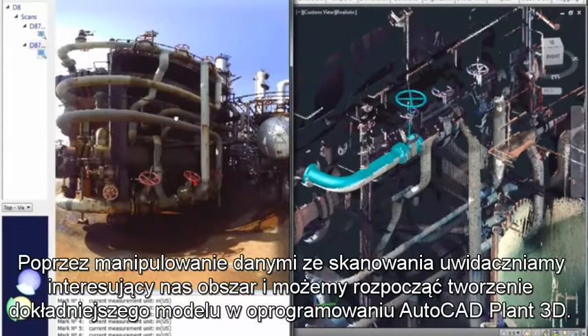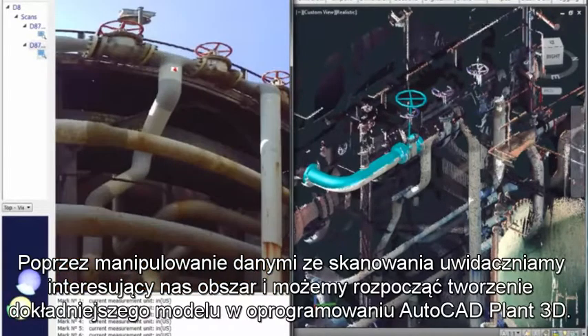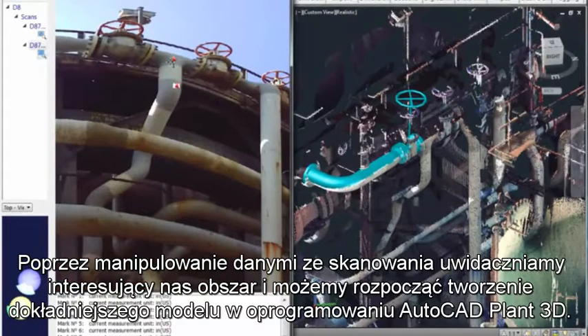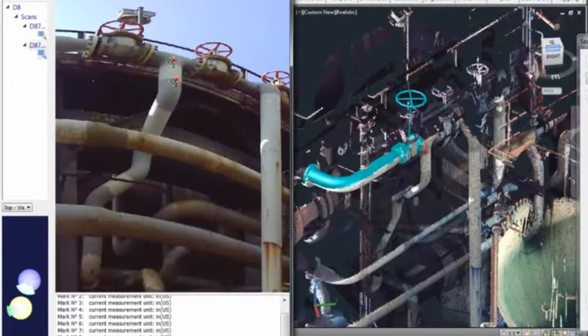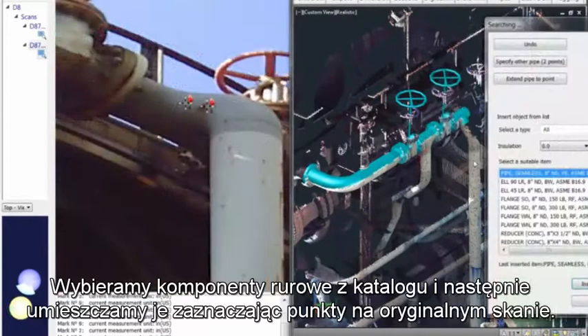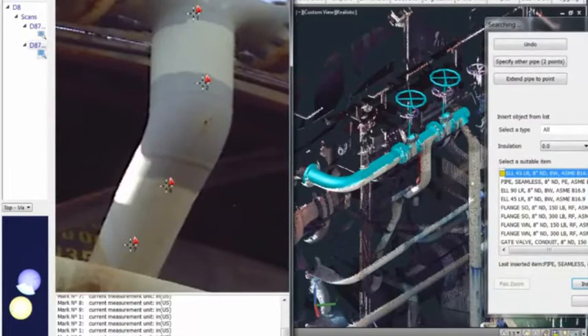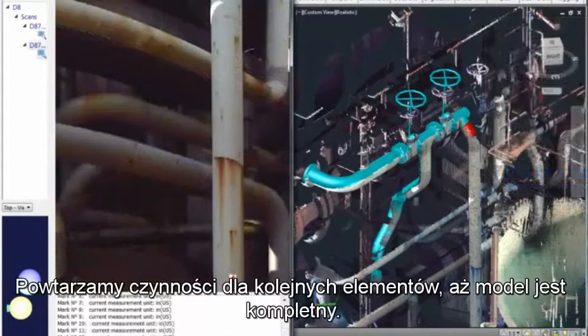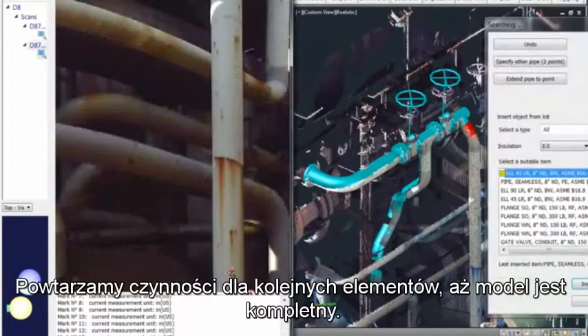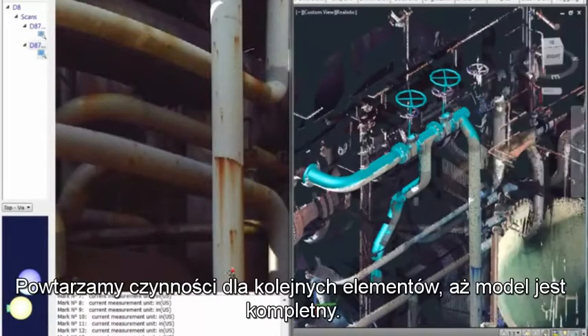By manipulating the scan data to focus on the area of attention, we can start to create a more accurate model in AutoCAD Plant 3D. We will select the piping component from the catalog and then place it by selecting points on the original scan. We repeat this process for all components and pipes until the model is completed.